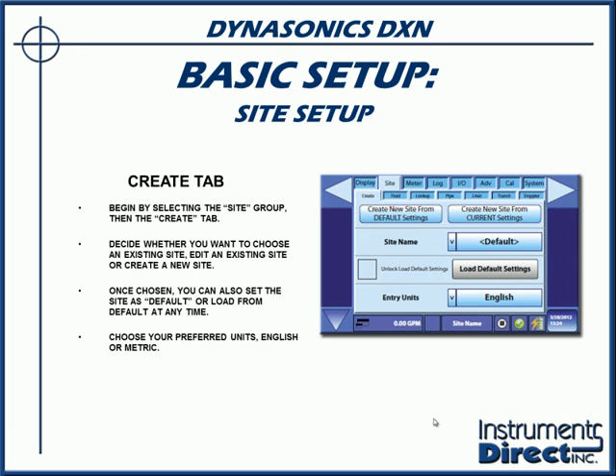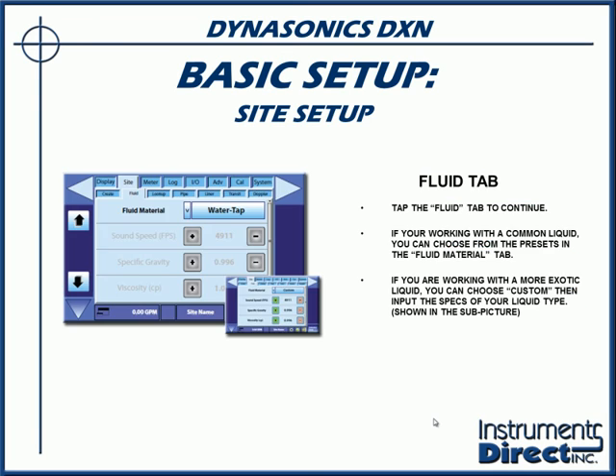So in this case, we're going to create our site, and then also at this level, we're going to decide whether we're going to use English or metric. And after we create and name our site, next we need to go over to the Fluid tab. In this case, it does have a drop-down menu of most of your common process liquids. So most of you out there are going to use the water setting almost all the time. Generally speaking, if you have a unique process chemical, it's probably on that chart. And if you don't have it on that chart, you can always give us a call.